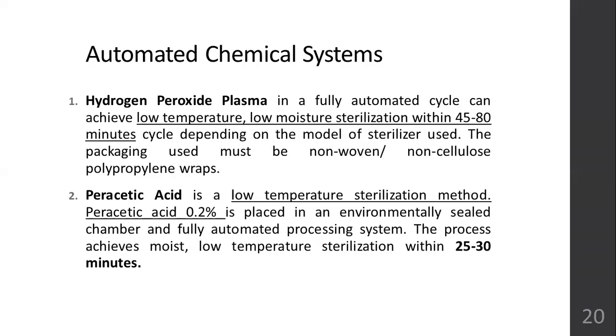Then you have automated chemical systems. Hydrogen peroxide plasma is one type of automated chemical system. Low temperature, low moisture sterilization within 45 to 80 minutes, quick. And packaging also should be done here; non-cellulose polypropylene wraps are used. Then peracetic acid plasma is another form of chemical system. Again, low temperature sterilization methods. Any instrument which cannot withstand high temperature, high pressure, or high moisture can be used here. 25 to 30 minutes it will take.